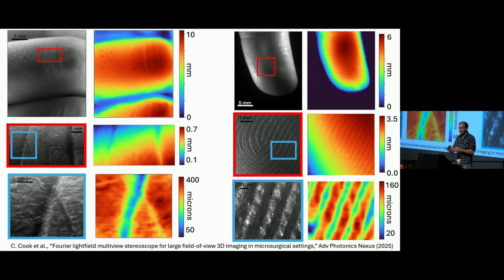And just resolution-wise, we get pretty high resolution. So we can zoom in and see the ridges of your fingerprint, for example. So it's in the tens of micrometers height resolution regime, which is suitable for a lot of applications in microsurgery.